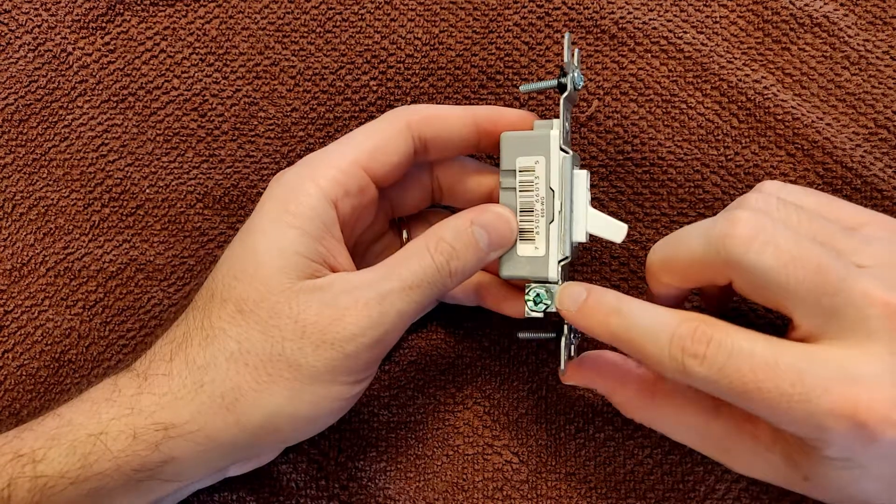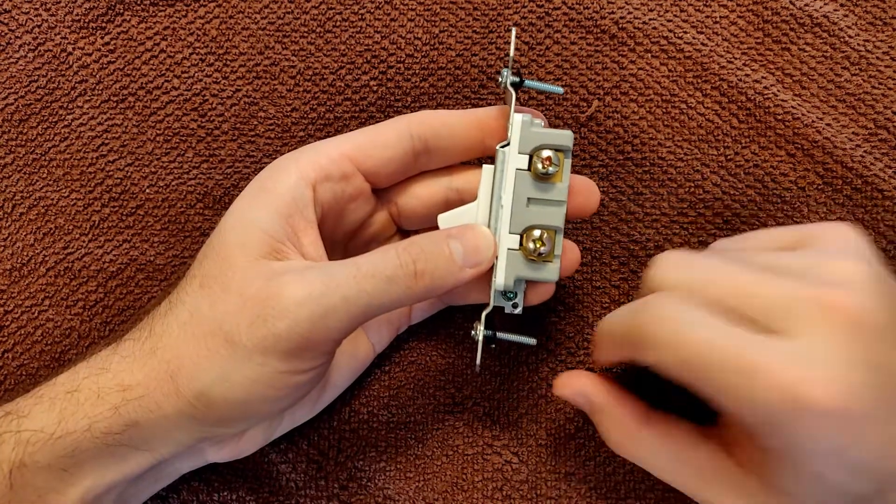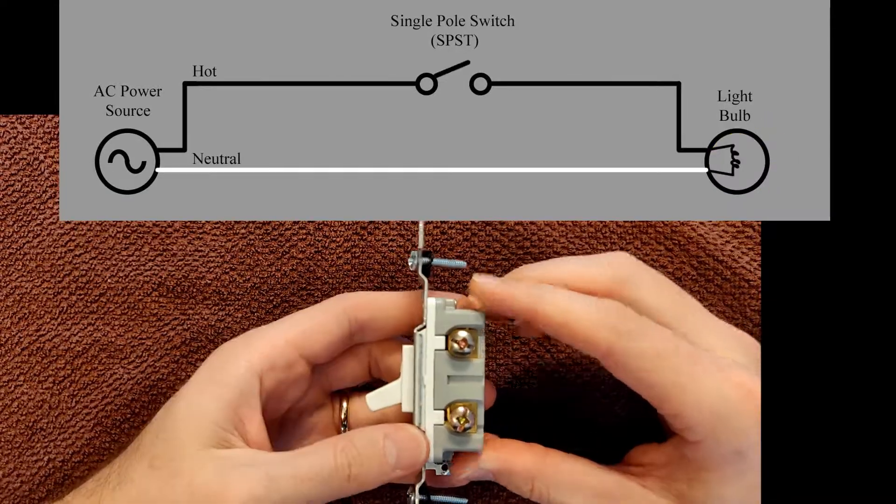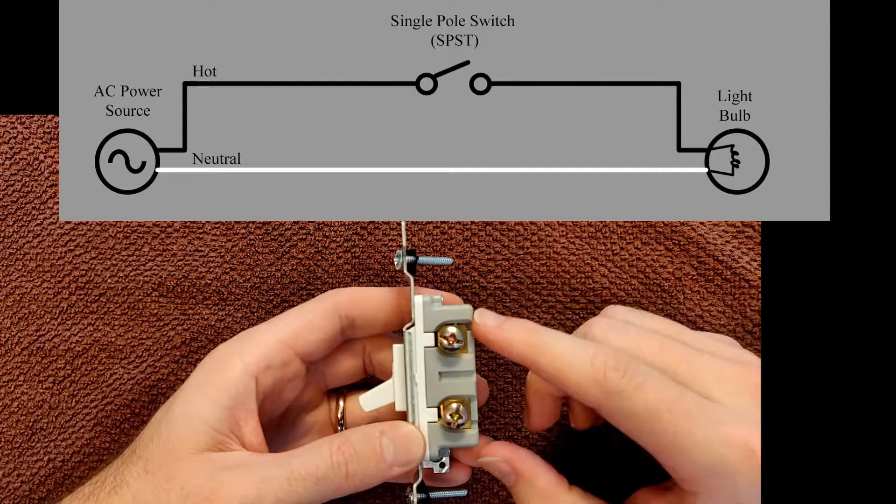A single-pole switch has one ground screw connected to the body and two hot screws. The power comes in at one hot screw, the switch turns it on or off, then the power goes out at the other screw towards your light fixture.